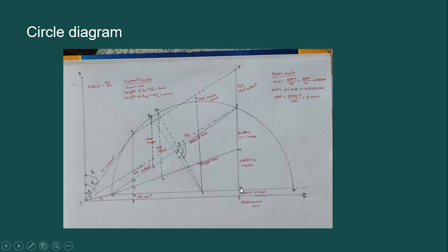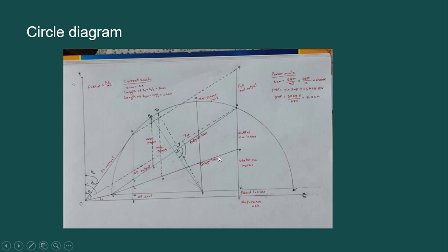Mark points K and J. The length from point K to J gives you the fixed losses. You also need to divide the length from G to K into two equal parts, because the rotor copper losses are exactly half of the total copper losses. Mark this midpoint as H. From point H, extend a line to O dash — this line gives you the torque line. The segment from H to G represents the rotor copper losses, and from H to K represents the stator copper losses.